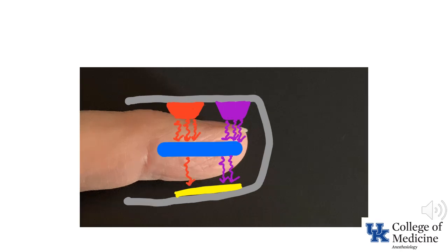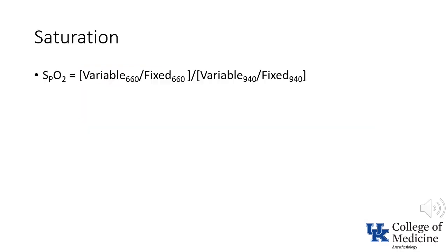In contrast, this illustration adds the element of deoxygenated blood as represented by the blue line overlying the finger. It shows that more of the red light is absorbed compared to the amount of infrared light that is absorbed. Effectively, what happens is that the pulse oximeter only looks at the red over infrared ratio for the pulsatile component of the signal.